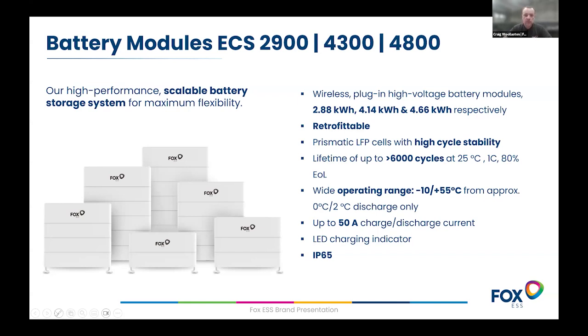Take the stack on the right - it's a 3-battery stack, each battery around 50 volts, so that's 150 volts total. You multiply that by the charge discharge current of the inverter. Let's take an H1, a simple single-phase domestic installation, which has a 40 amp rate of charge discharge. With 3 batteries at 150 volts, that's around 6 kilowatts of continuous charge discharge. In that example, using an H1, that's more than what the inverter can output, since we're talking about 3.75 and 6 kilowatt inverters.